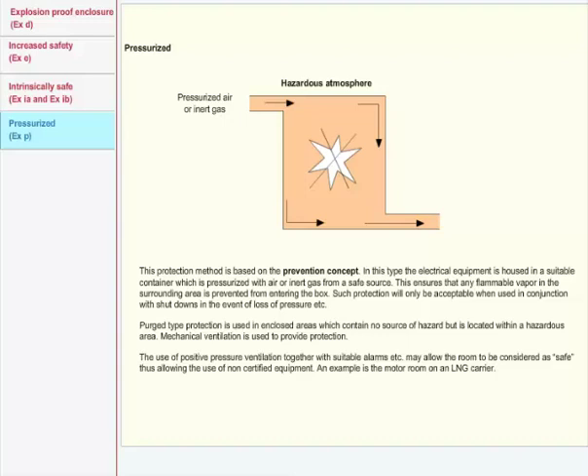Purged type protection is used in enclosed areas which contain no source of hazard but are located within a hazardous area. Mechanical ventilation is used to provide protection. The use of positive pressure ventilation together with suitable alarms, etc. may allow the room to be considered as safe, thus allowing the use of non-certified equipment. An example is the motor room on an LNG carrier.